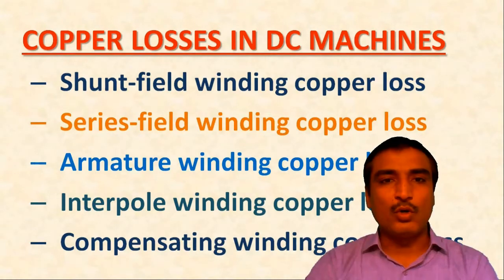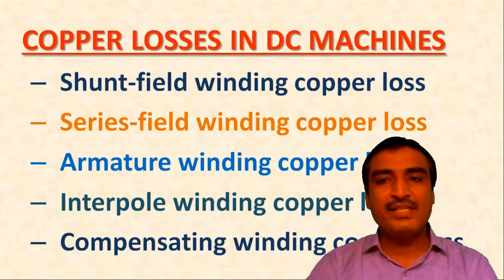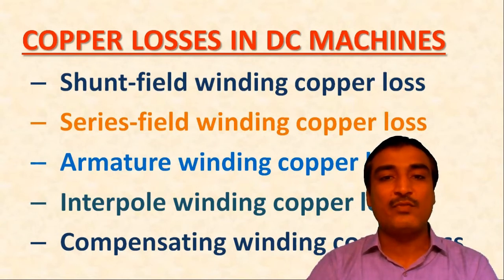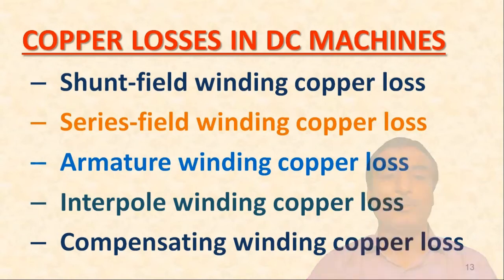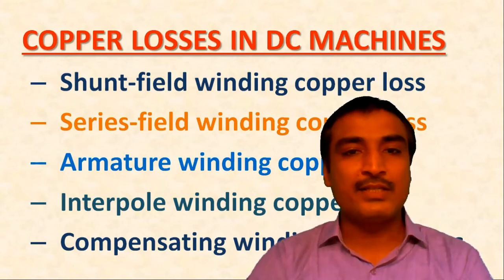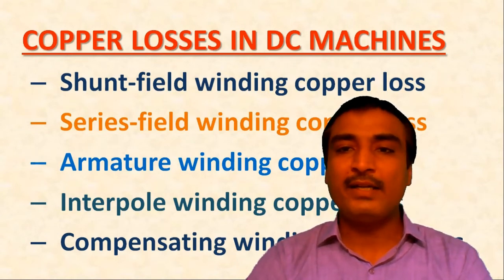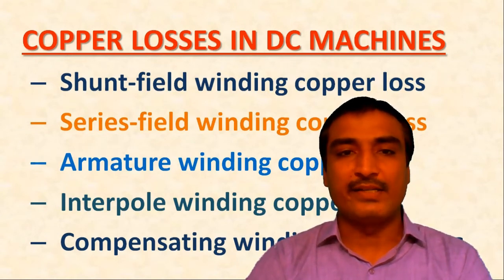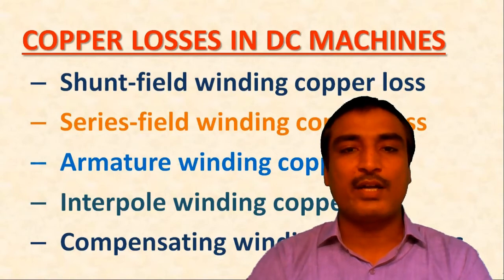Furthermore, it is worth noting that the series field, interpole, and compensating windings are connected in series with the armature of the DC machine and thus they carry full armature current. For this reason, the copper losses in the series field, interpole, and compensating windings are proportional to the square of the armature current.